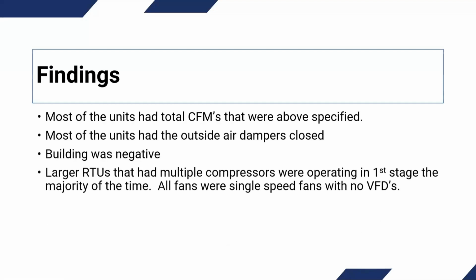One of the major things that we saw are the larger RTUs that had multiple compressors and 2 and 3 stage units. The majority of the time they were operating in first stage, which is common. Even now when we see digital scroll compressors and MSAV type RTUs, they typically are going to be operating on the lower end of the spectrum of capacity. The problem we have with these larger RTUs on this particular project is they were all single speed fans. None of the fans had VFDs. None of the fans were ECM motors. There was no way to adjust the speed except through pulley adjustments, sheave changes or adjusting the sheaves. So no matter what stage the unit was in, it was always delivering the maximum CFM that it was capable of delivering.